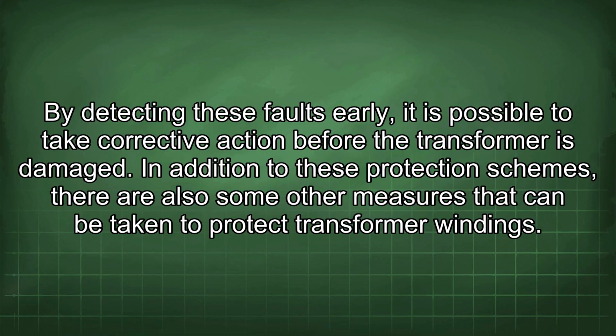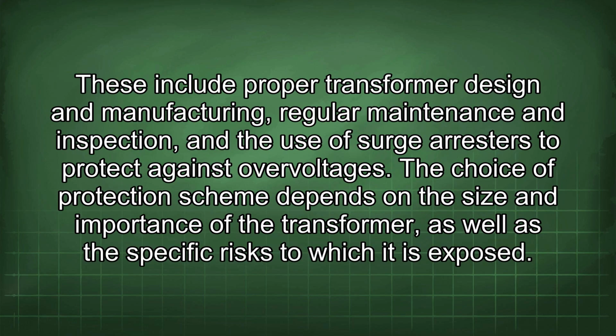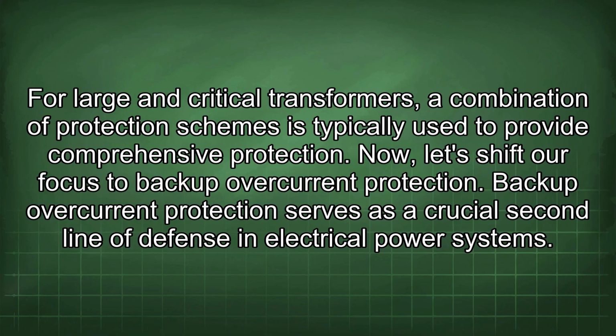In addition to these protection schemes, there are also some other measures that can be taken to protect transformer windings. These include proper transformer design and manufacturing, regular maintenance and inspection, and the use of surge arresters to protect against overvoltages. The choice of protection scheme depends on the size and importance of the transformer, as well as the specific risks to which it is exposed. For large and critical transformers, a combination of protection schemes is typically used to provide comprehensive protection.